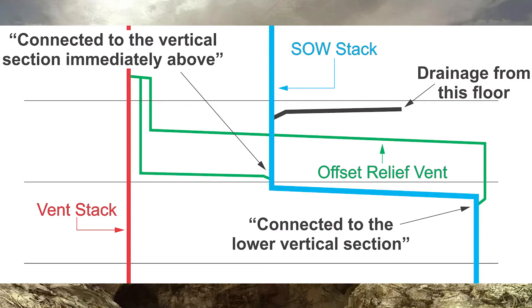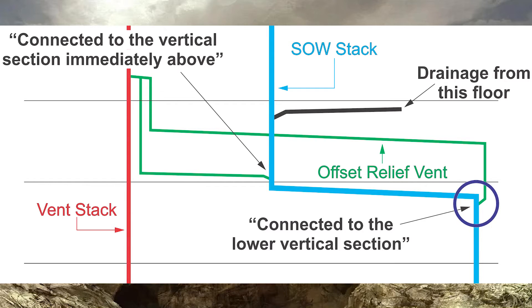The next part of that clause talks about where we take a vent off for the lower portion of the offset. There are two different options — let's look at both. Part A talks about connected to the lower vertical section at or above the highest soil or waste pipe connection. Looking at this picture, my offset turns down and goes vertical, and I'm just going to put a Y right underneath that point, just like I have in the picture here.